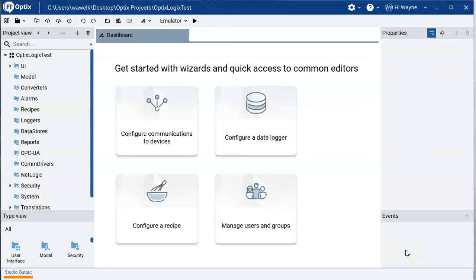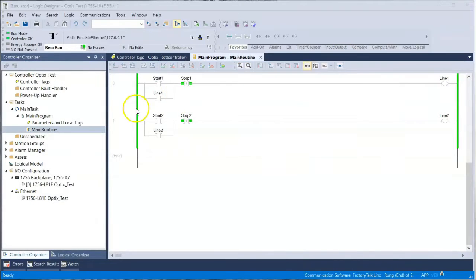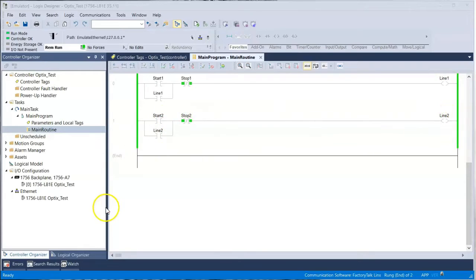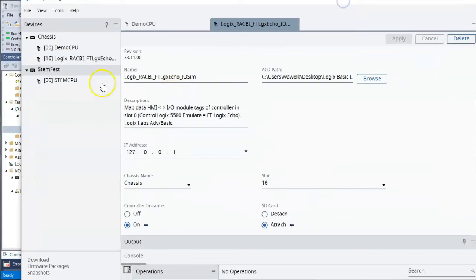Now we're inside the project and inside Optix Studio, ready to develop our application. Two things we'll do: first, set our COM driver to tie it to our Logix controller, and second, create a simple screen with push button objects to watch it interface. In the background I have a Logix controller pre-built with two simple rungs — one to start Line 1 and one to start Line 2, a simple latch circuit — running in the Logix Echo emulator at 127.0.0.1.